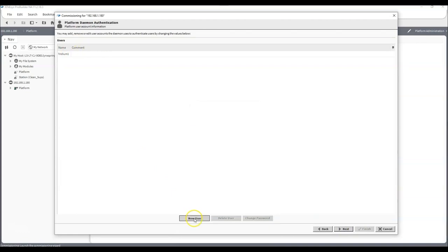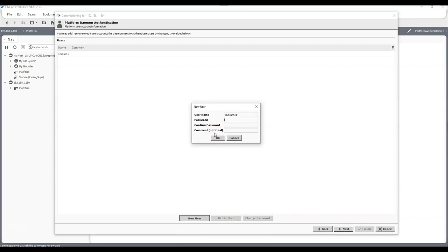And we've already added one user, but we'll add another. In this case here, we're going to use the owner. I've seen a lot of contractors only use one platform name, and I always give the owner, whoever actually bought the controls for the building, a username and password, and it's important to do that, especially because this is a Niagara product, other Niagara integrators may be available.